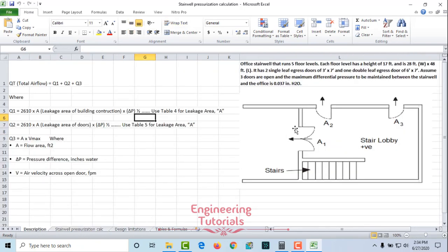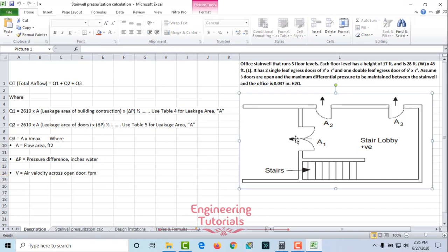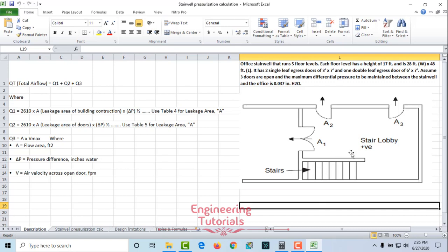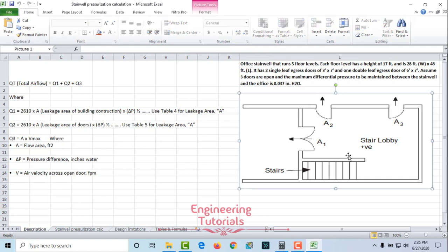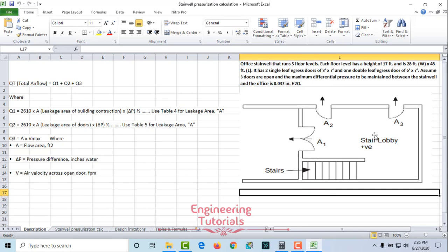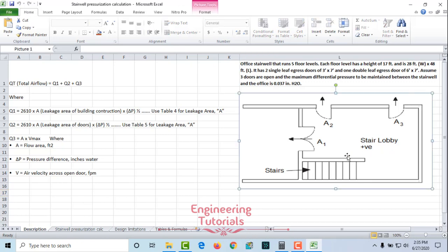Before starting the design, you need to understand what a stairwell pressurization system is. It is basically intended to prevent smoke leakage through doors into the stairs by injecting clean air into the stairwell. The purpose is to provide the highest pressure in the stairwell area with respect to the adjacent space, providing a safe escape path for occupants and firefighters. In a case of fire, this area will be positively pressurized so no smoke will enter through the doors into the stairwell.